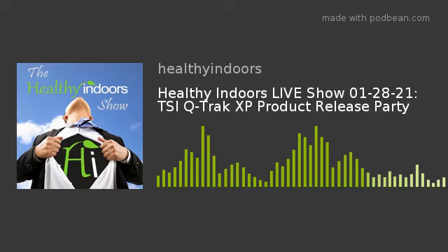Some of our users have said that they calibrate their instruments daily, some weekly, others dependent on the kind of work they're doing, if they need that validation for their customers or for their application for the record keeping. And what we built into the GUI interface is a very easy process of selecting a sensor to calibrate and then allowing for that to be done either via gas flow or with direct input of readings, if you're trying to match with, say, a master temperature reading that you have that is highly accurate that you depend on, then you can enter that as well and calibrate it directly to that. So we've looked at that from a calibration and maintenance from a variety of different angles.